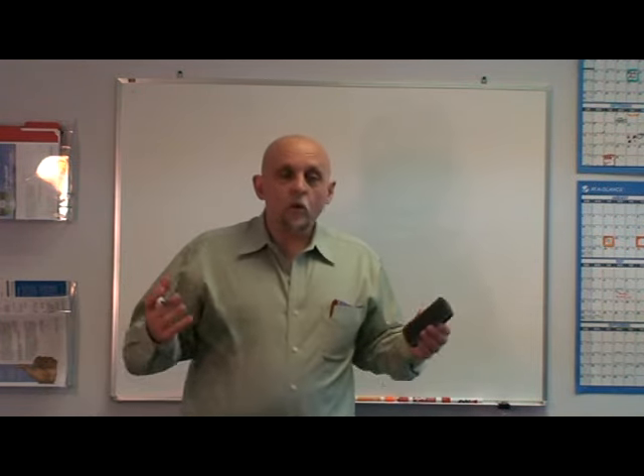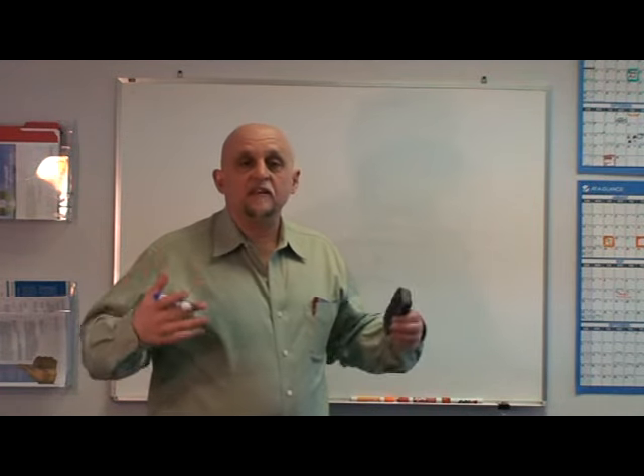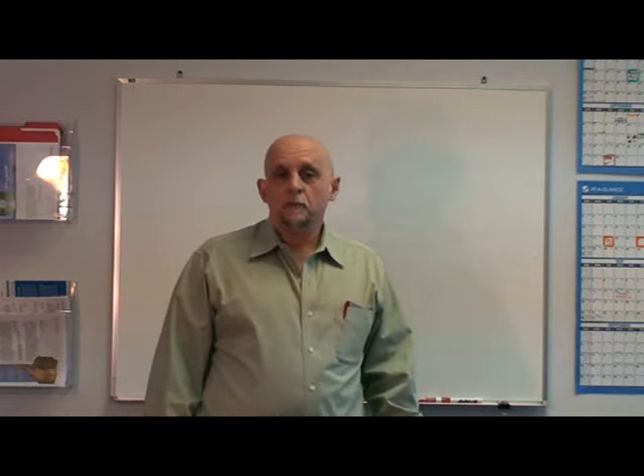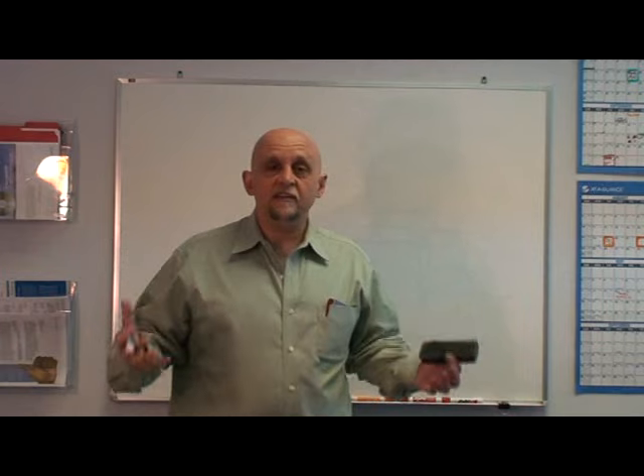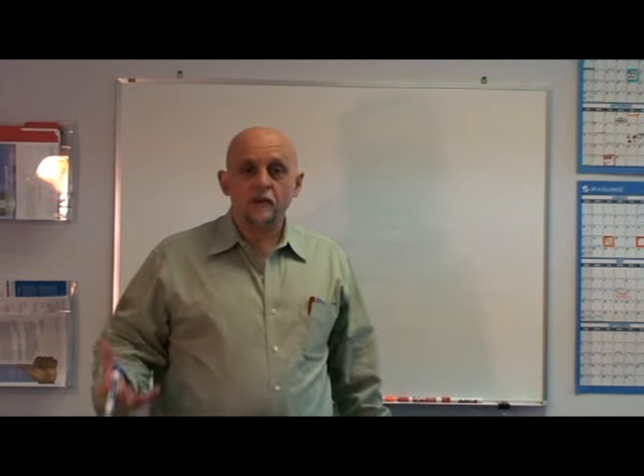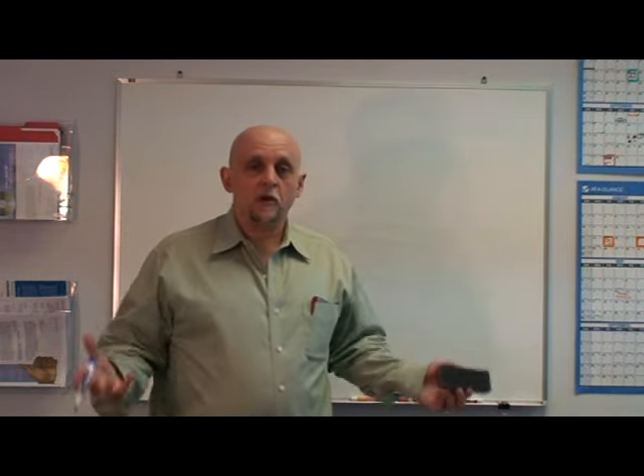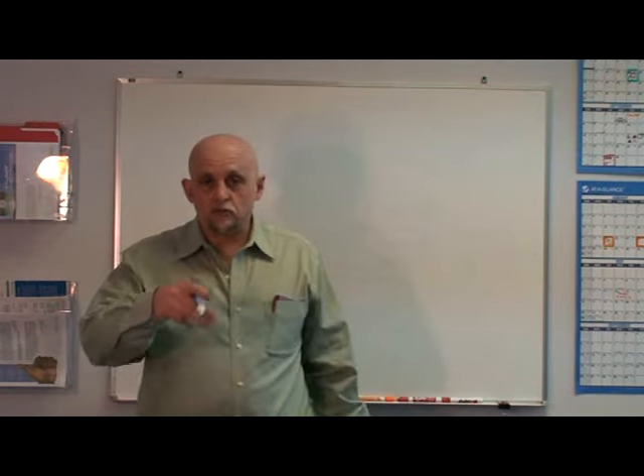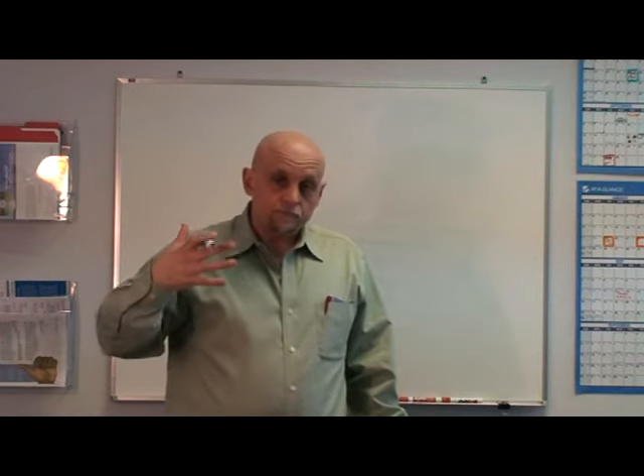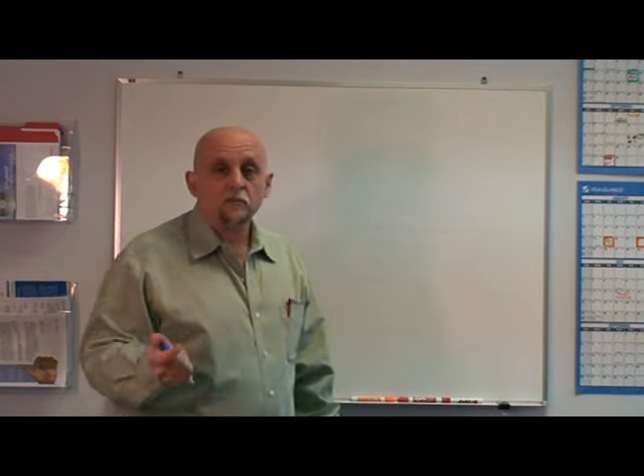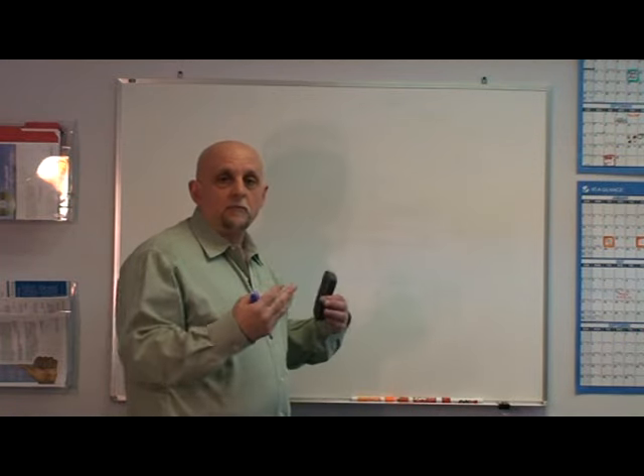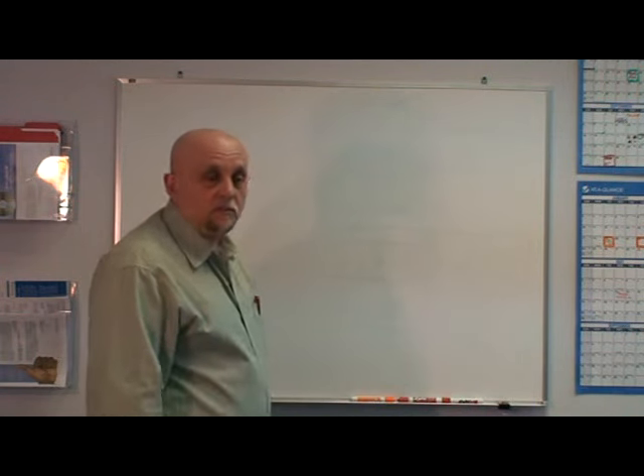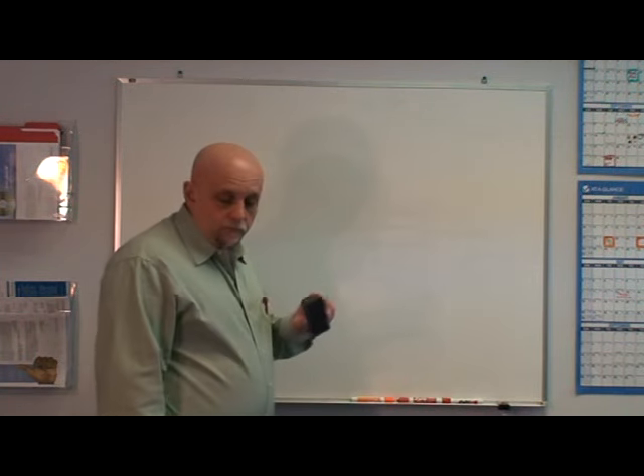So first thing to talk about is, number one, why Modbus RTU? Well, Modbus RTU has been around since like Columbus came to America. I think Columbus had it on the Santa Maria. Why is it around so long, and it's in everything? There's probably hundreds and hundreds of thousands of nodes that have Modbus, and Modbus RTU specifically, because all you need is a serial port and an RS-485 driver to make your device a Modbus RTU device. So it's been used in everything, and it's a very simple packet, as I'll show you in a minute. So a lot of people have implemented it. That's why it's important to you, because if you implement Modbus RTU, then you can talk to this wide variety of devices that speak Modbus RTU.